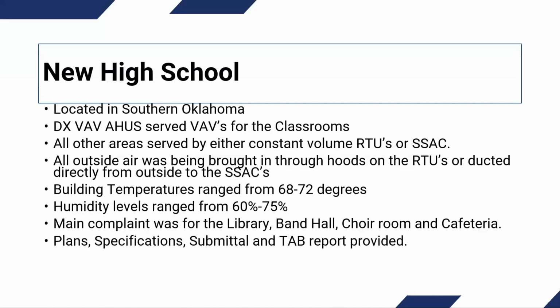Again, when we start, we always make sure we have plan, specification, and submittal, and they provided us the TAB report. Again, this TAB report was done by a NEB company, which is no longer in business. And we didn't bother looking at the TAB report. I will say on both the jobs that were performed by NEB companies that we did not do, there was no water data in the first report. We knew that from our testing, they didn't do the water, and there was no water data provided. So at least they didn't falsify the data. And on this particular school, there were no temperatures. They had air readings, but they didn't have any temperature readings on any of the equipment.